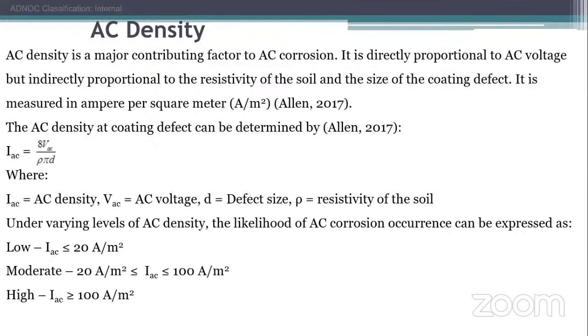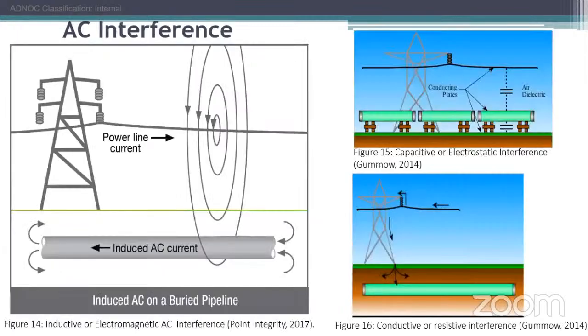So our task now is to look at this: if we are able to reduce the communication between the transmission line and the pipeline by keeping them far apart, the induced voltage in the pipeline will be reduced. If the induced voltage is reduced, the density will be low, and we are discontinuing the AC corrosion from happening. If the resistivity of the soil is increased, or the coating defect is increased, we're also reducing the AC density tendency.